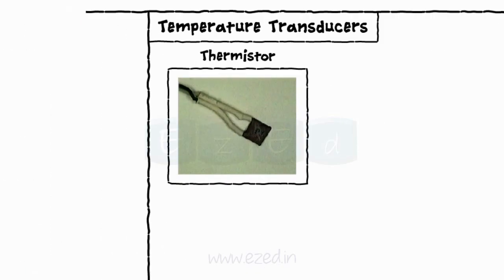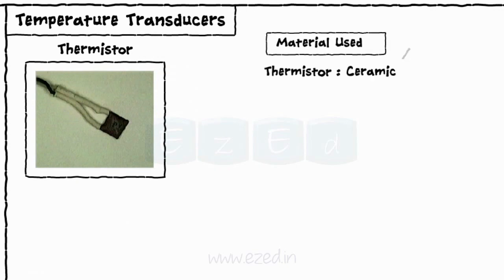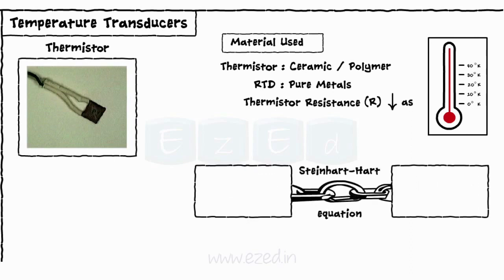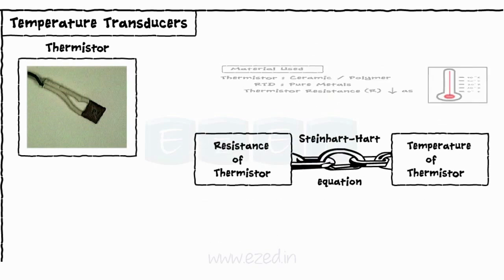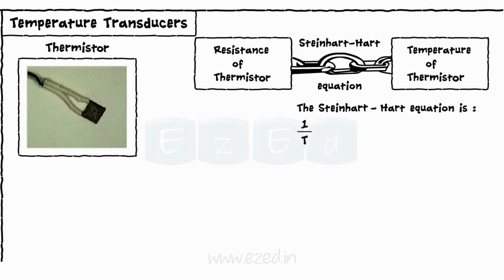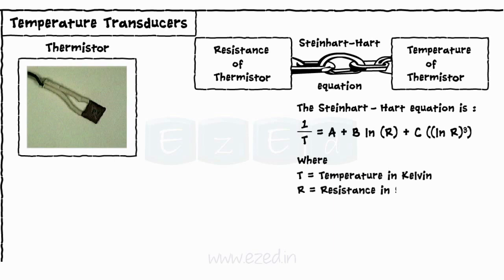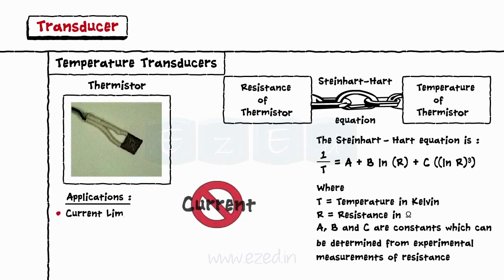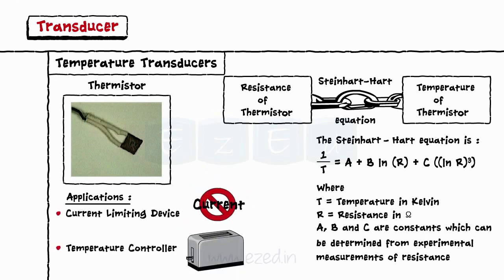Thermistors differ from RTDs. The material used in a thermistor is generally ceramic or polymer, while RTDs use pure metals. Thermistors are made up of semiconductor materials, so the resistance of a thermistor decreases with increase in temperature. Using the Steinhart-Hart equation, we can calculate the temperature of the thermistor from the measured resistance. The Steinhart-Hart equation is: 1/T equals A + B·ln(R) + C·ln(R)³, where T is temperature in Kelvin, R is resistance in Ohms, and A, B, and C are constants determined from experimental measurements. Common applications of thermistors include use as a current limiting device and for temperature control in toasters, coffee makers, etc.